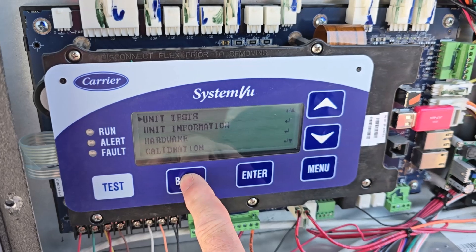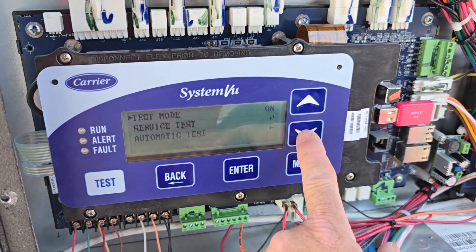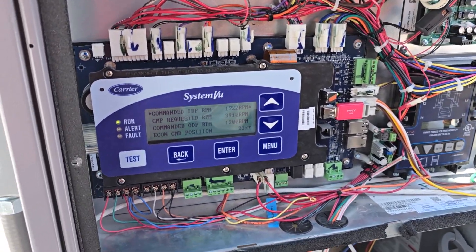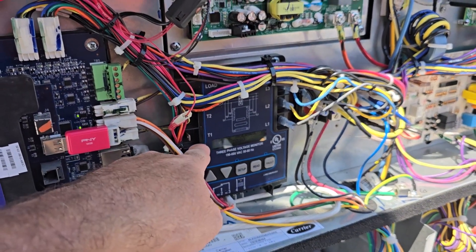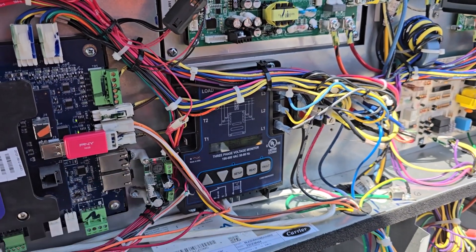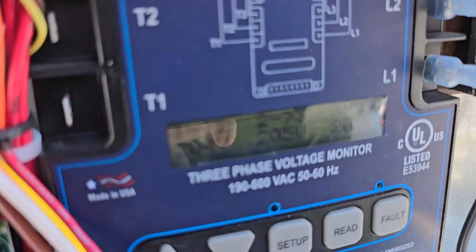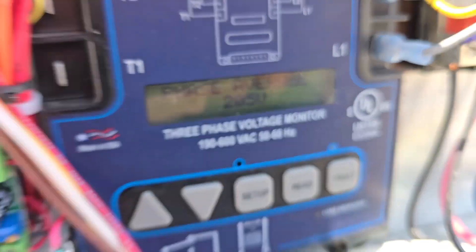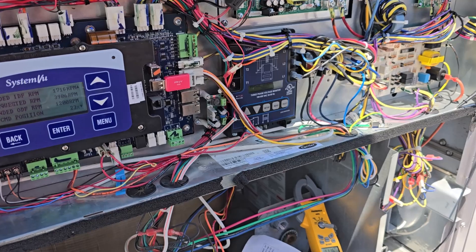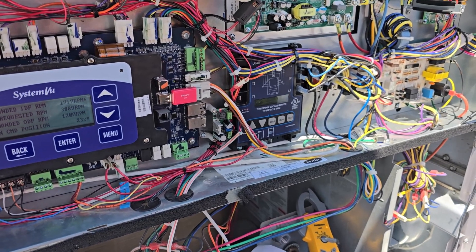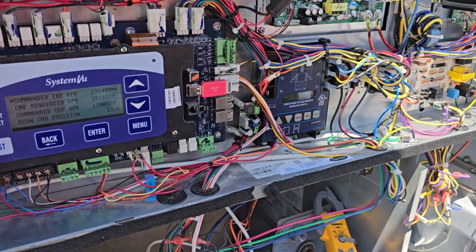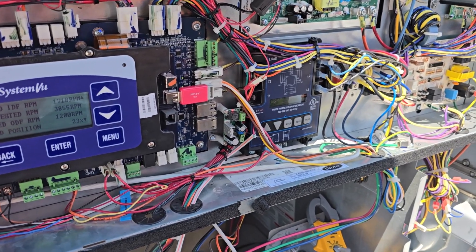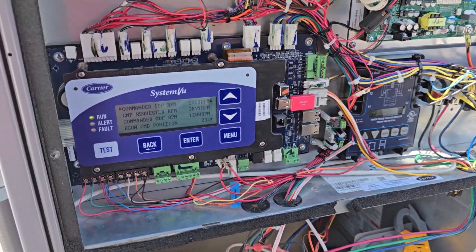I added the three-phase monitor just to check because it's kind of in an area that might have some questionable voltage issues. There were some faults in there when I got here today, but I don't know if that was generated from technicians working on it or not. So I went ahead and wiped those out so it's starting fresh. This says auto test and complete, press enter to continue. I had to widen the tolerance a little bit for the under voltage just because we seem to be getting about 204 to 205 volts average here on this site. So it tripped right in front of us when it dropped down like to 201 or 202. So I just widened it up to 5% which will give us like a 10 volt drop from 208 nominal.